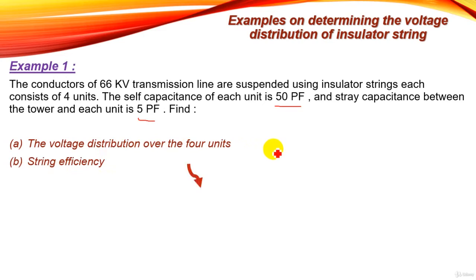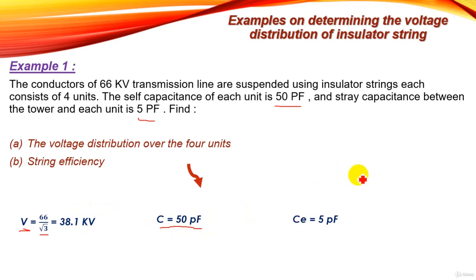First, the givens: the total voltage is 66 kilovolt, but this is line-to-line voltage. To convert to phase voltage, we divide 66 kV by root 3, obtaining 38.1 kilovolt. The self-capacitance equals 50 picofarad and stray capacitance equals 5 picofarad. From these two values we can deduce the m factor: m equals 5 over 50, so m equals 0.1.